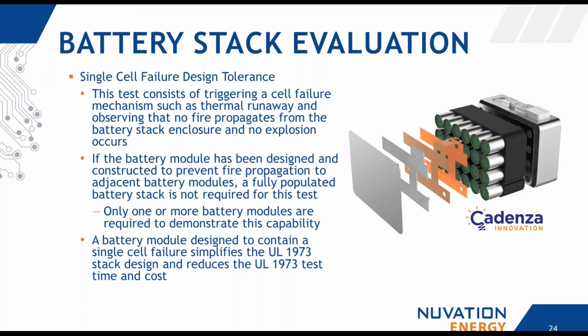If instead a battery module is used and that battery module has been designed such that it contains the heat energy produced by that cell, then only the module needs to undergo that test. And it's really just to prove that no propagation occurs beyond that. And that allows for a simpler rack design, since the energy to contain within the battery stack enclosure is kept to a minimum. You're not worrying about your entire energy capacity being converted into thermal heat that then has to be contained by your outside enclosure, because each module handles that for you.